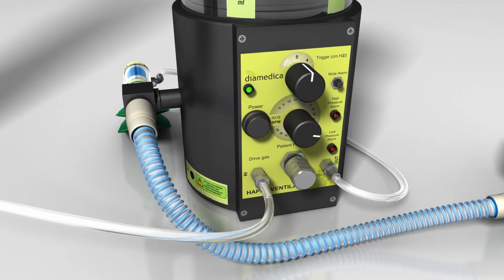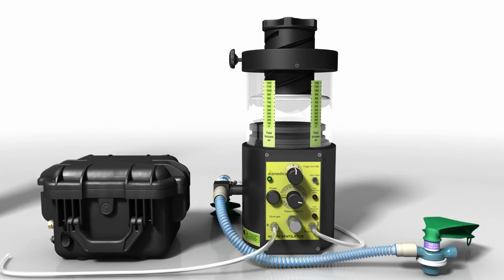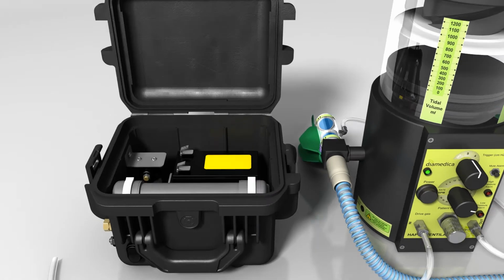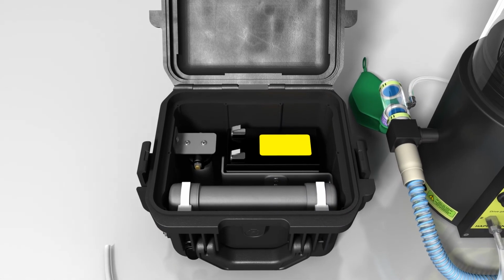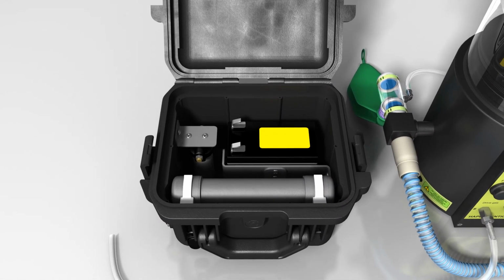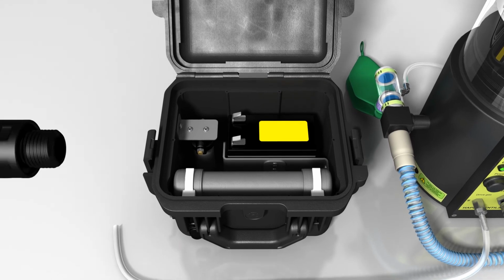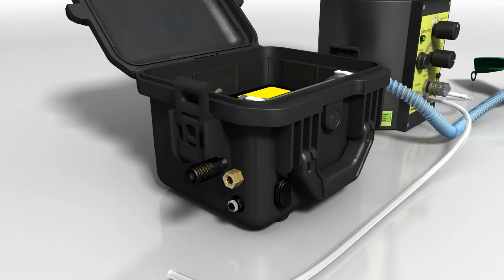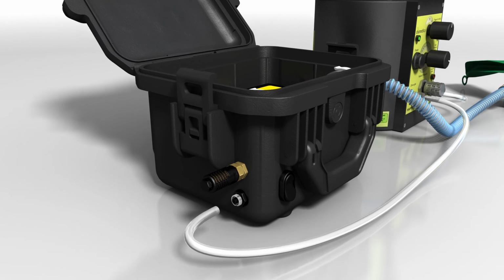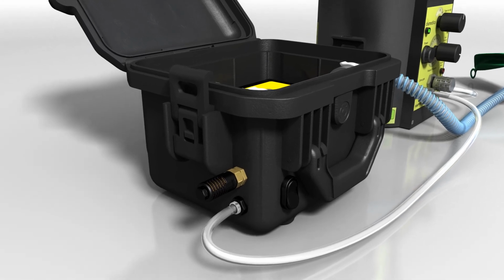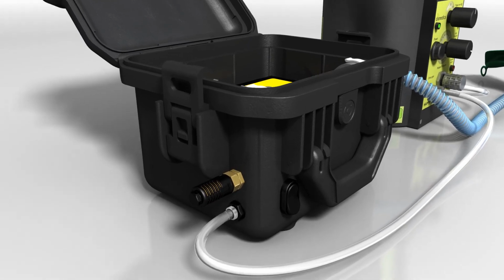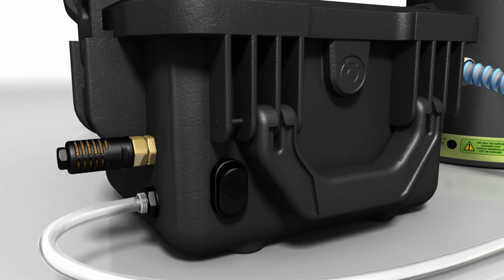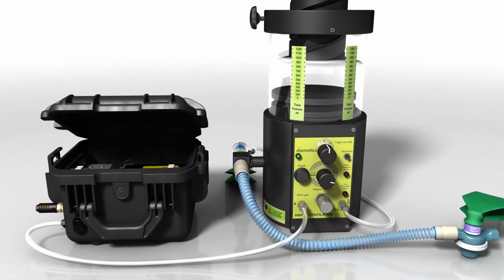If no oxygen source is available, a compressor pump using air can be used to drive the ventilator. The compressor pump contains a pump, small reservoir, and a lead-acid rechargeable battery and water trap. The inlet filter is first screwed into place and the drive gas tube connected between the pump and the ventilator. The pump is then switched on. The battery should run for 20 hours when fully charged.